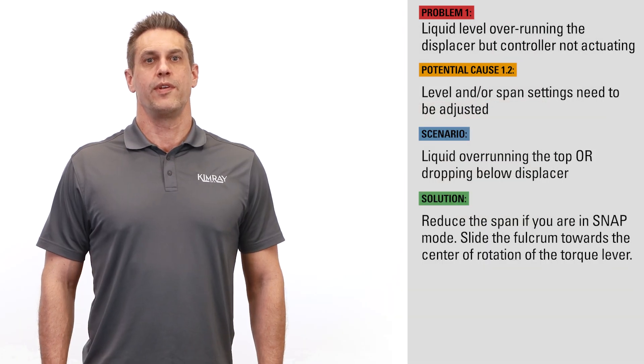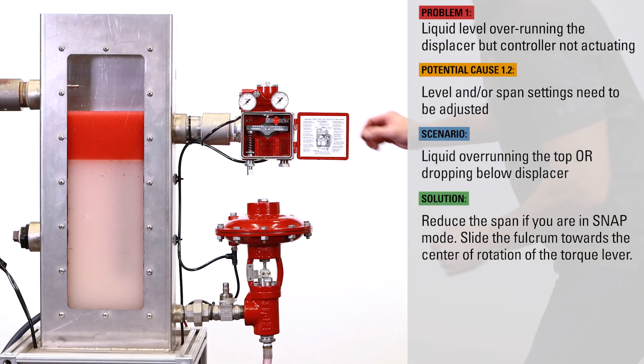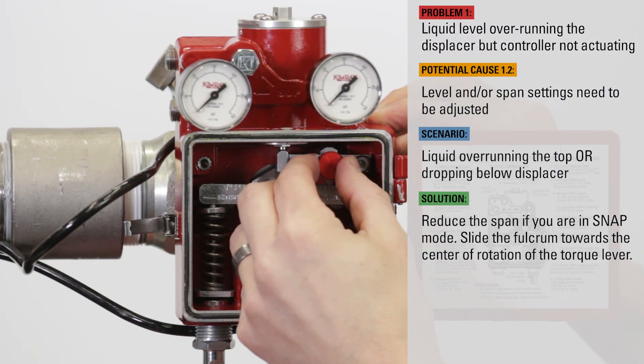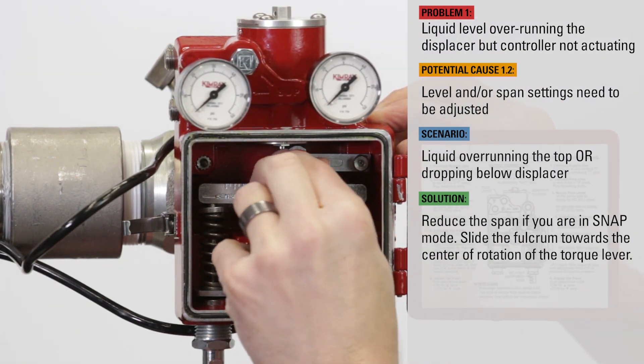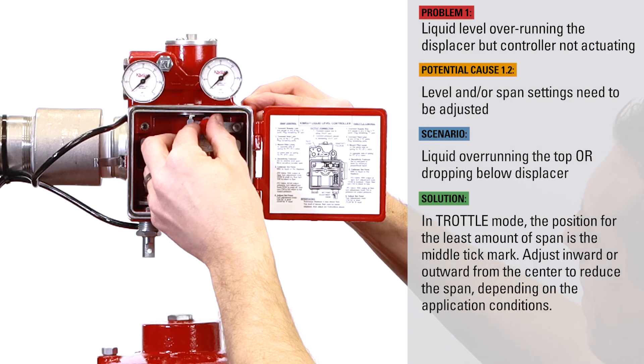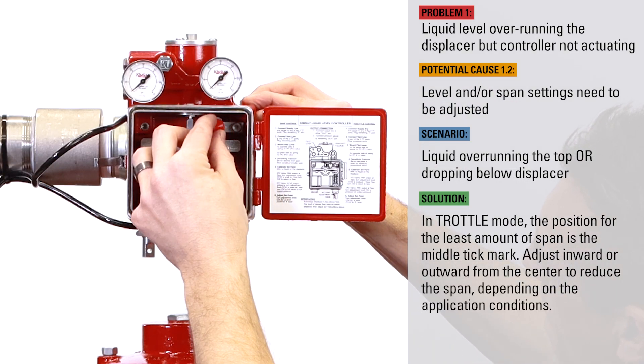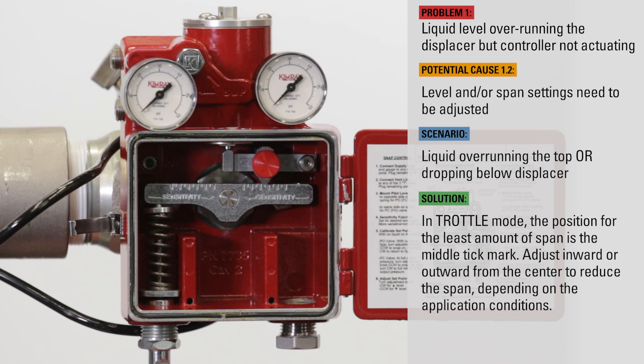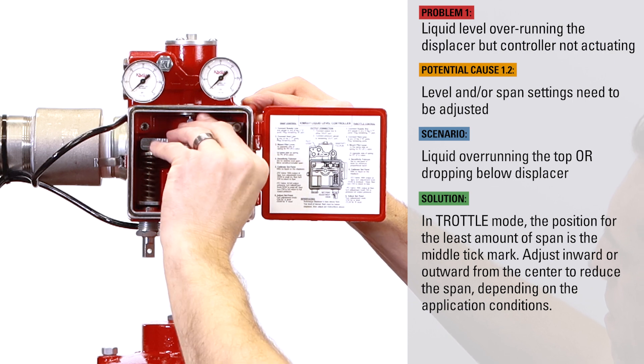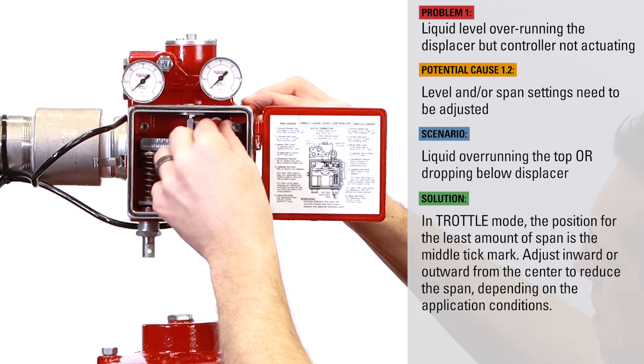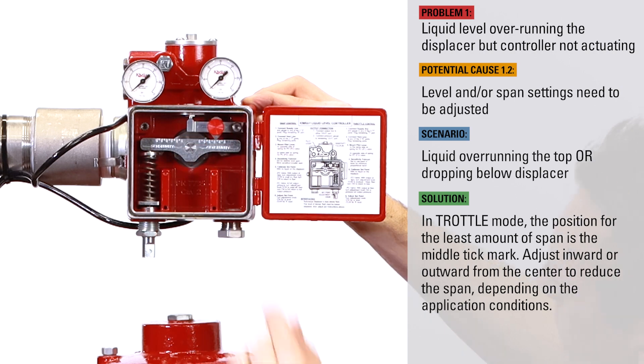You may also need to reduce the span. If you're in snap mode, this can be done by sliding the fulcrum towards the center of rotation of the torque lever. In throttle mode, span setting would typically not be the issue, but as a rule of thumb, the position for the least amount of span in throttle mode is the middle tick mark, but adjusting it inward or outward from the center tick mark could reduce the span depending on the application conditions.